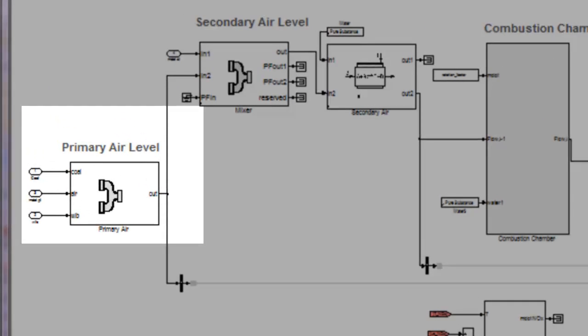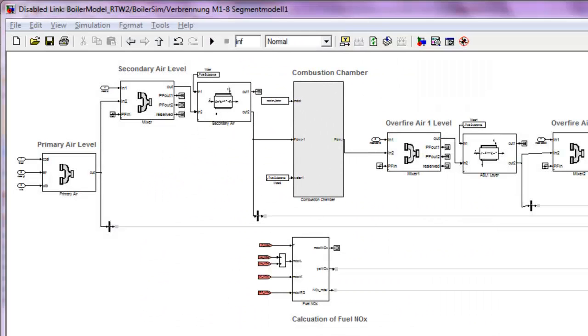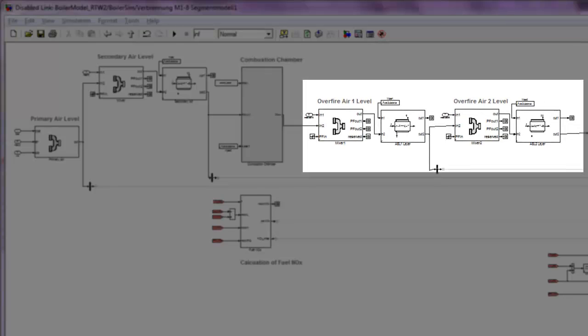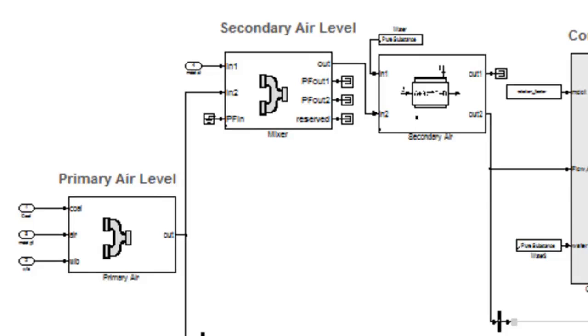The different levels of combustion are modeled. We have primary air, secondary air, the combustion chamber itself, and in this case of this particular power plant, the overfire levels one and two. At the primary level, air and coal are mixed but no reaction takes place. At the secondary level, additional air is mixed into the coal, and at this point combustion starts to take place.